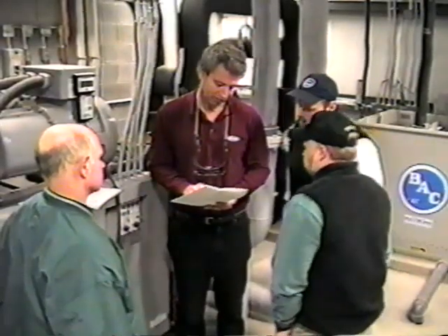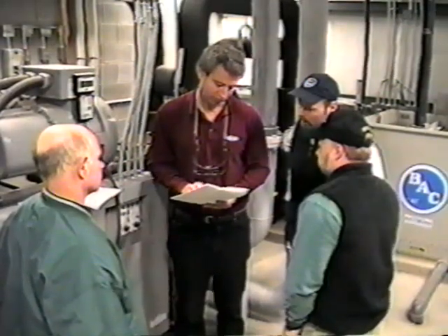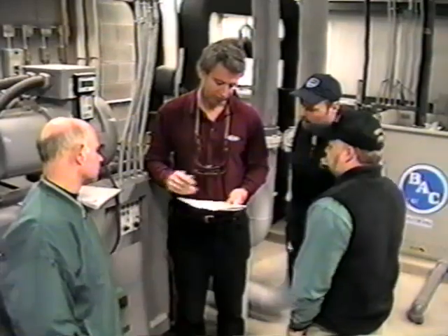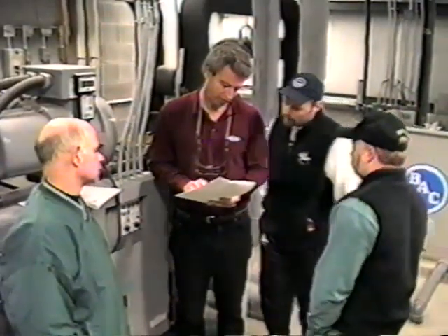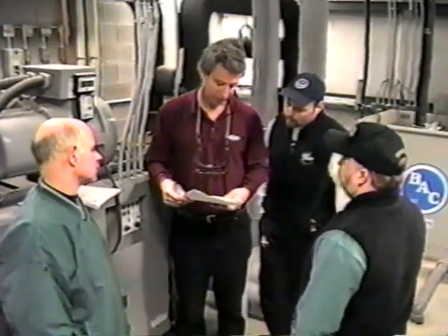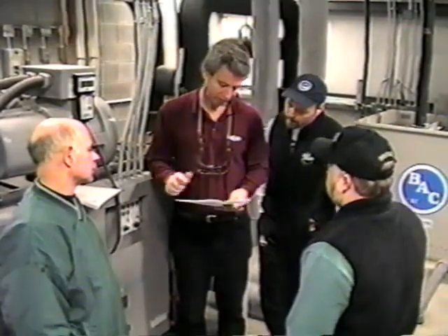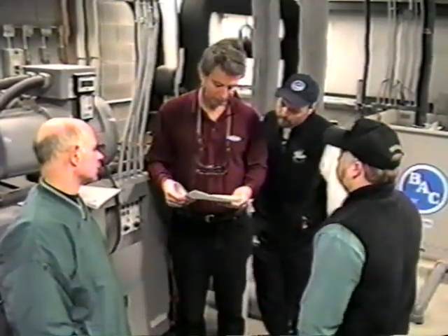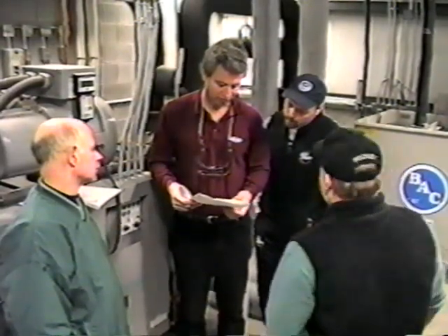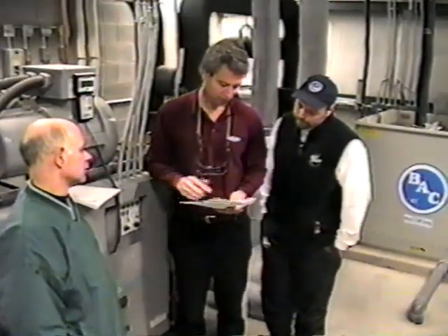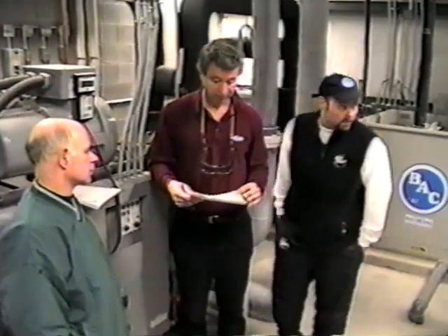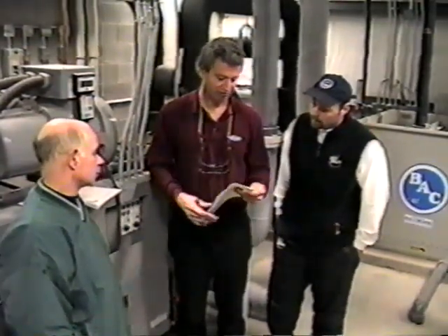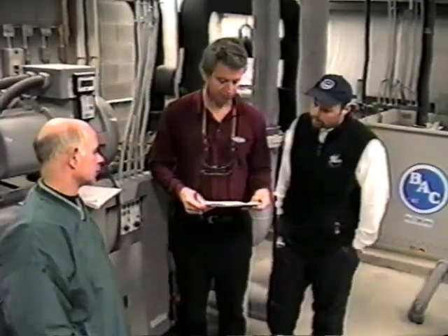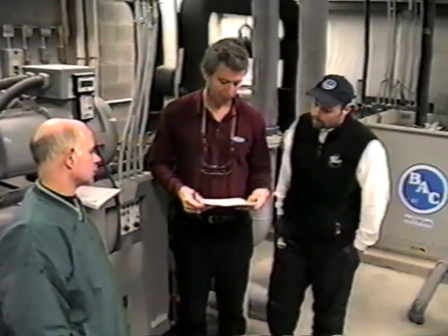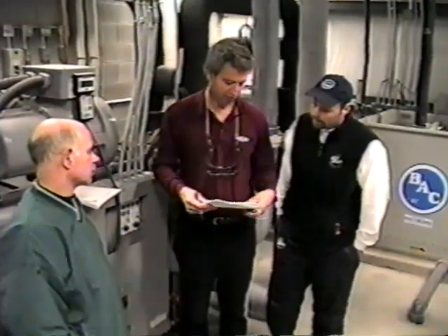These two, the A and the B, the running current. And this menu shows suction, cooler, discharge. Cooler level indicators are important too. So these three items on this mode: compressor A running current, you've got cooler level A, compressor A running current, cooler level B, compressor B running current. And again, there may be only one compressor running, so it may not be as bad as it looks. These really, I don't think on a regular basis you need to log these.